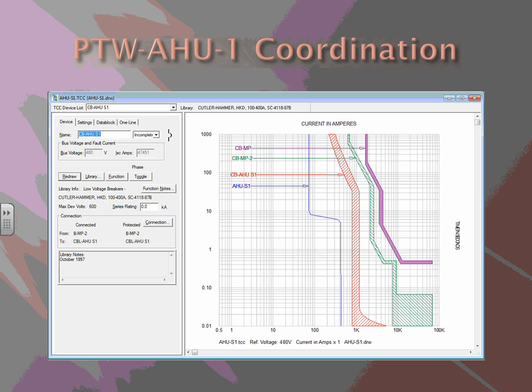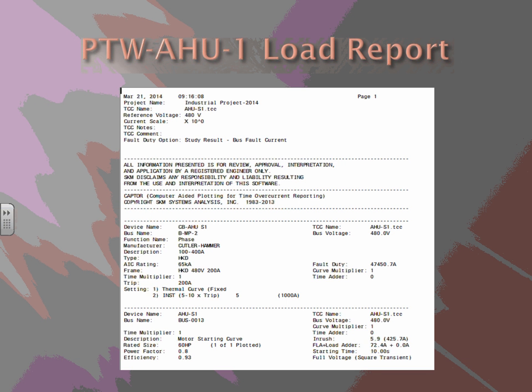Coordination curve, air handling unit, fully coordinated here, showing the main breaker, and then mechanical panel 2 curve along with the air handling unit circuit breaker, and the actual unit itself. Load report for that air handling unit. I'm giving all the Cutler-Hammer we use 100 to 400 amp, 65 K.